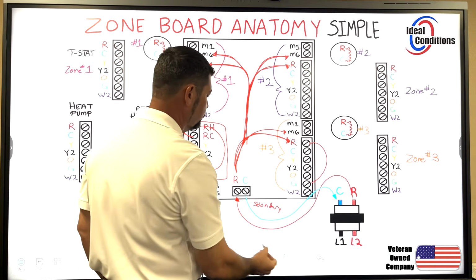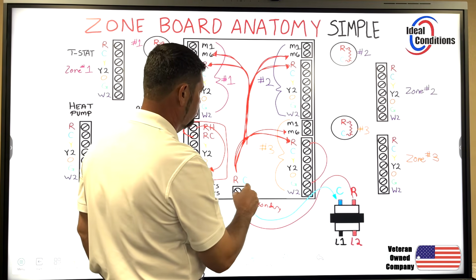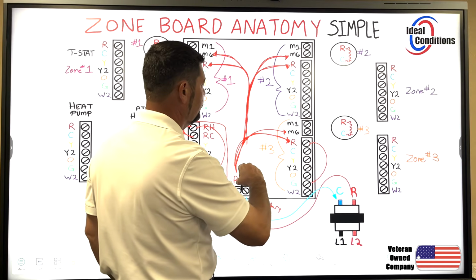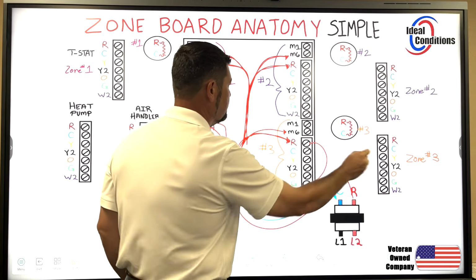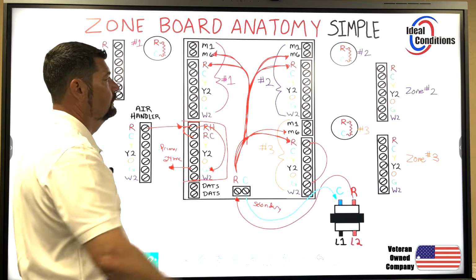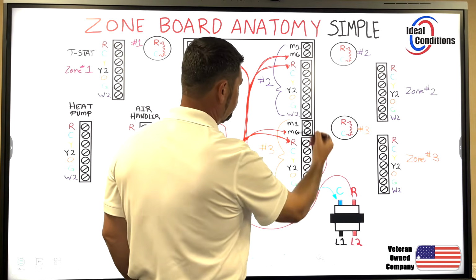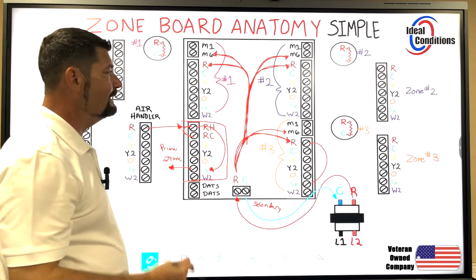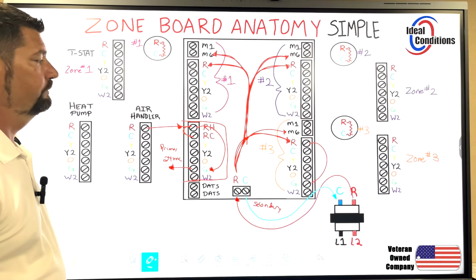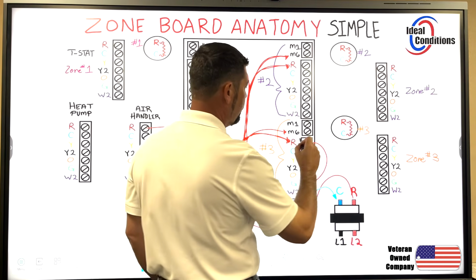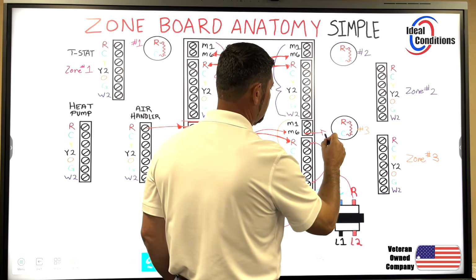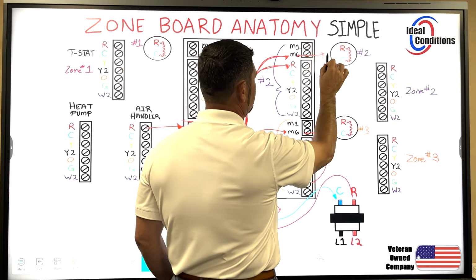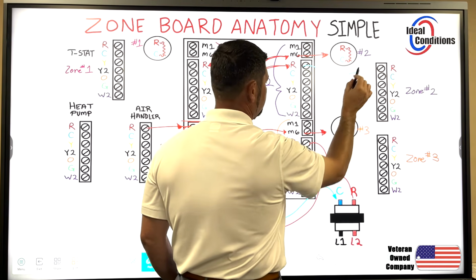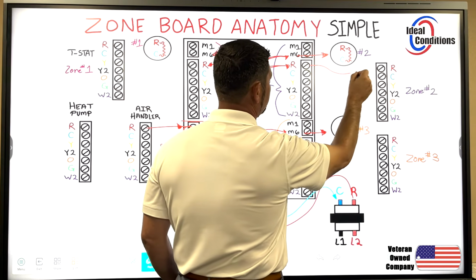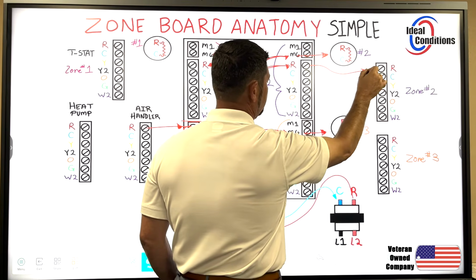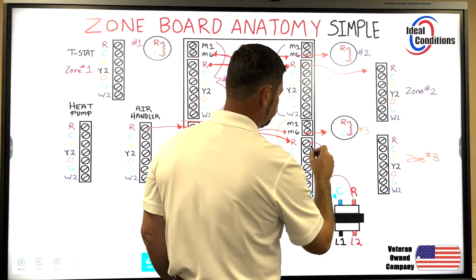Because the secondary transformer is sending power here to light up the zone board, and the secondary transformer is what is energizing all these thermostats and these dampers. All right? And so everything else that I have here on the zone board is an input. The zone board only puts power out on M6, right? It sends power out on red, 24 volt primary, right?